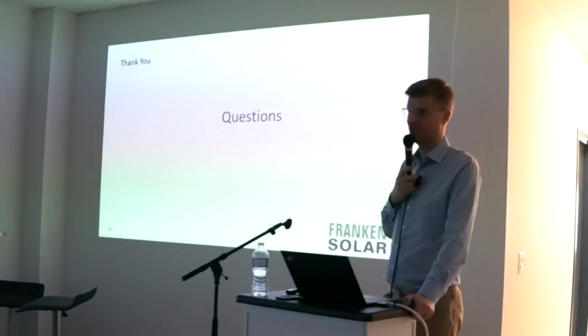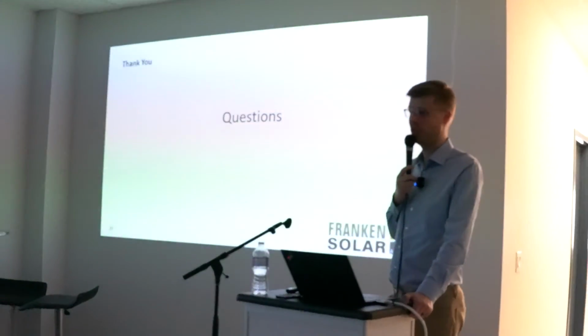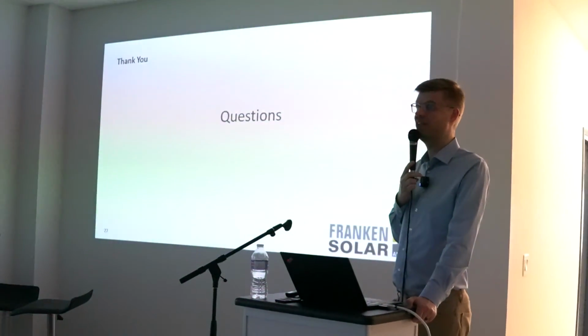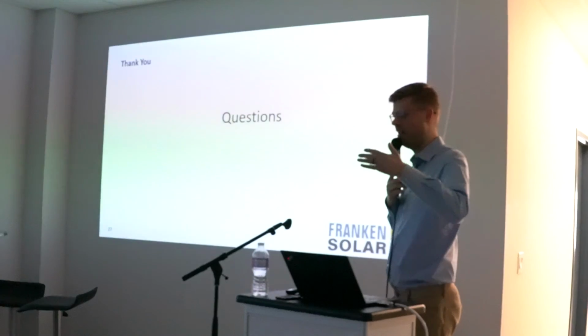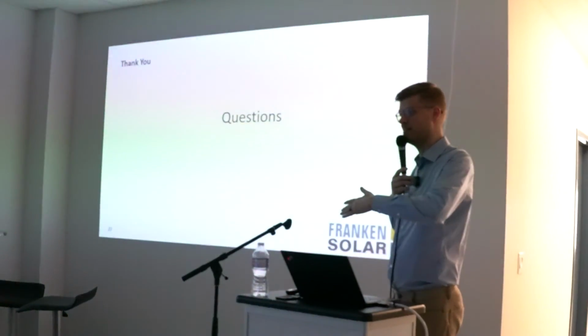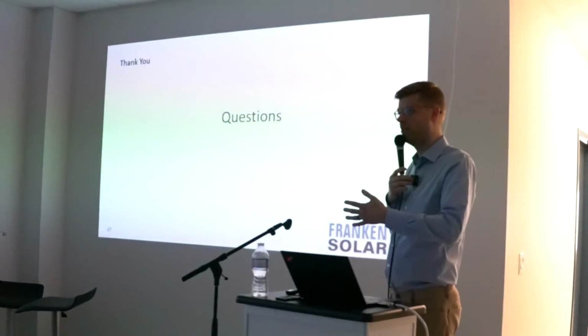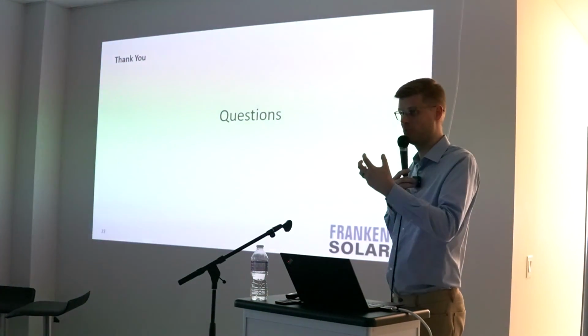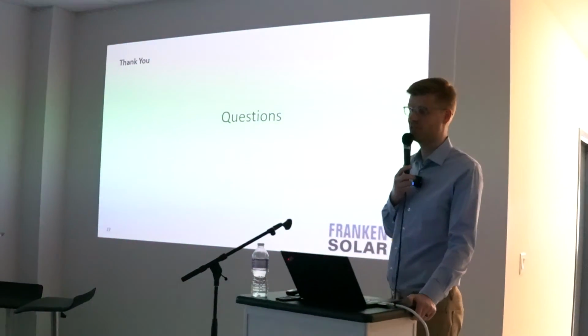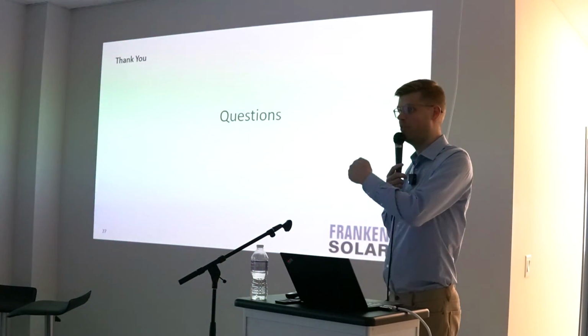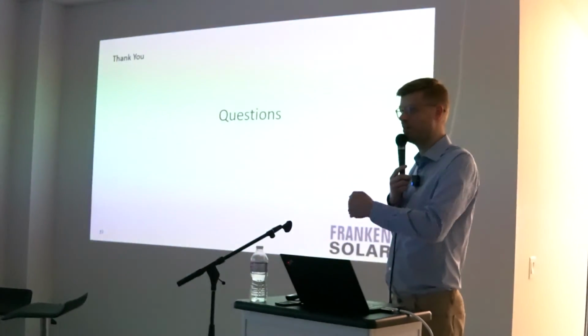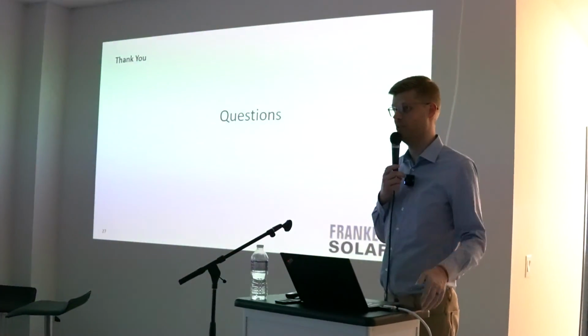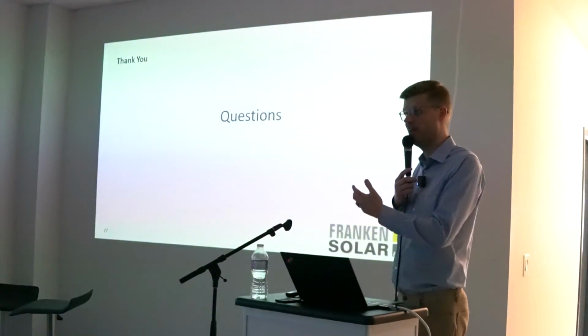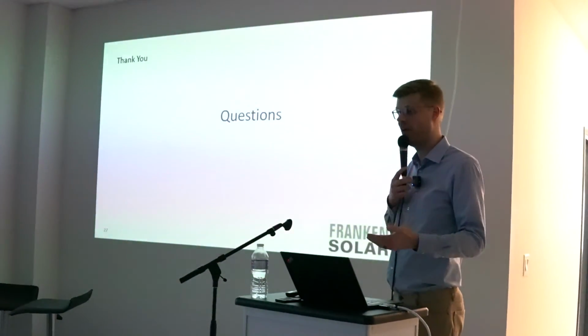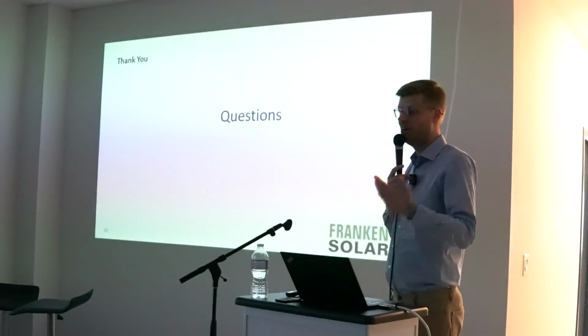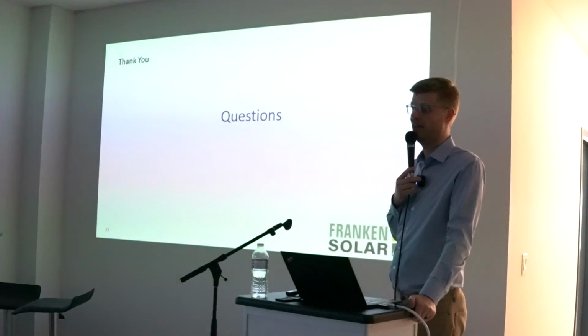For lead acid, we have the opposite effect. Lead over the last 24 months or maybe 3 years got significantly more expensive, to the point where a battery bank on lead acid is not that cheap anymore compared to a similar capacity, from a usable perspective, in lithium iron chemistry. So the decision to go to a lithium iron chemistry with the new players and the reduction in cost is much, much easier than it was probably 4 or 5 years ago. That's why the market and market volume in battery modules for 48 or even higher voltage systems is exploding compared to the previous sales volume in lead acid.